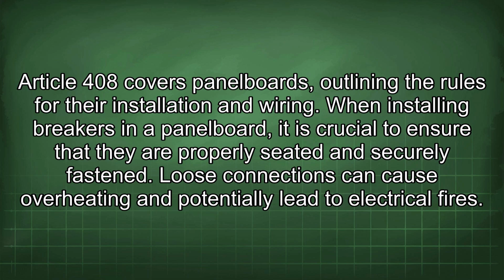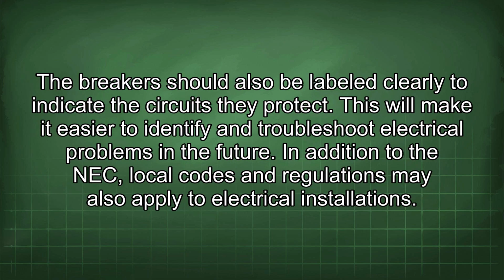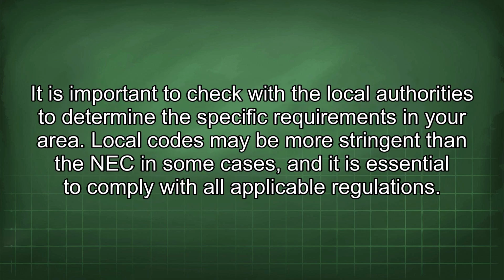Article 408 covers panel boards, outlining the rules for their installation and wiring. When installing breakers in a panel board, it is crucial to ensure that they are properly seated and securely fastened. Loose connections can cause overheating and potentially lead to electrical fires. The breakers should also be labeled clearly to indicate the circuits they protect. This will make it easier to identify and troubleshoot electrical problems in the future. In addition to the NEC, local codes and regulations may also apply to electrical installations. It is important to check with the local authorities to determine the specific requirements in your area. Local codes may be more stringent than the NEC in some cases, and it is essential to comply with all applicable regulations.